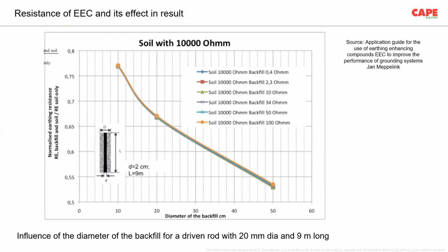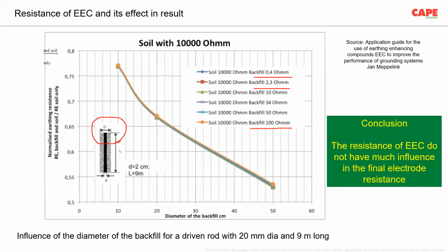Similarly, a lot of times people ask a question whether the resistance of an earth enhancing compound really influences the final RE value. Again, from the same paper, they have done research on backfill compounds of 0.4 ohm meter, 2.3 ohm meter, and 100 ohm meter. So different backfill compounds are used for an earth electrode of constant diameter, and you can see here the final resistance values are similar. So the conclusion is the resistivity of the earth enhancing compound does not have much influence on the final electrode resistance.